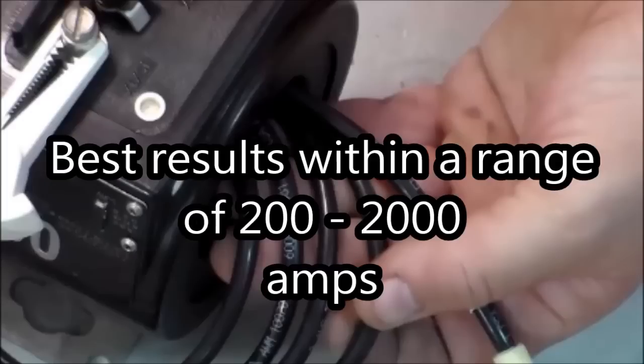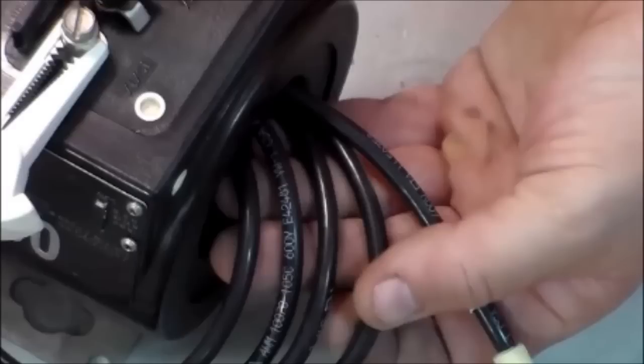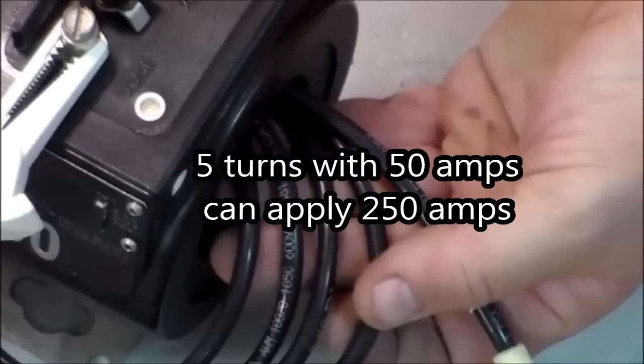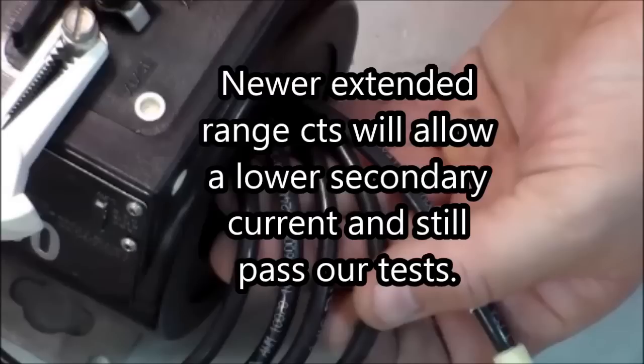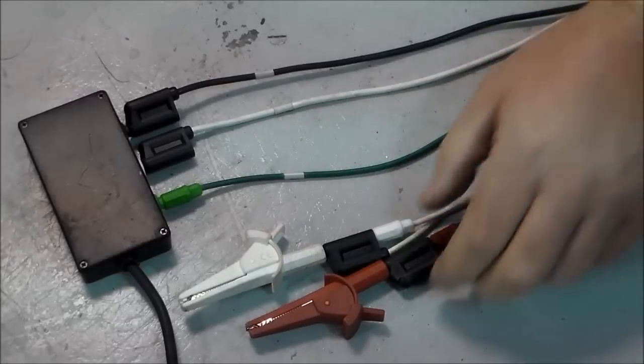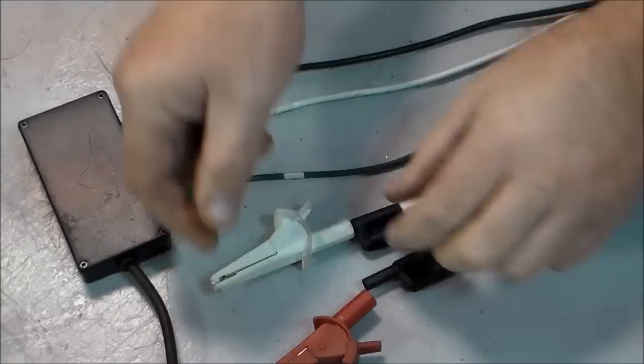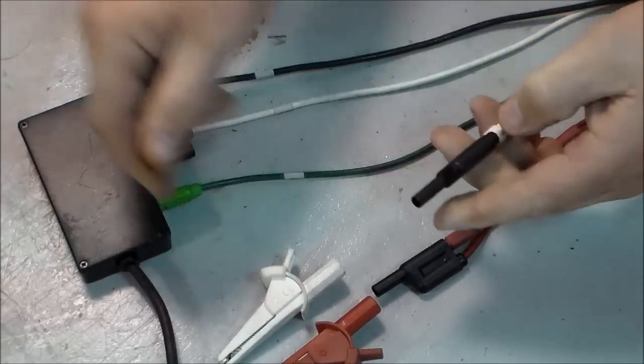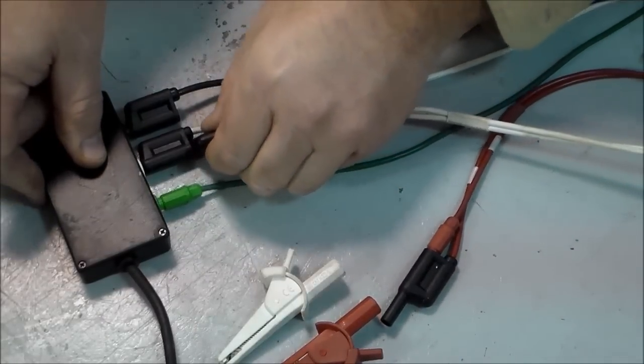As we move into the really large CTs, say a 2000 to 5 for example, we're approaching an upper limit of our test set. Again, we're going to see the best results in that window of accuracy, but in this case, we're not going to be able to get to the 2000 amps. About the max you can get is 250 amps, but that should still be able to test 99% of our CTs. Keep in mind the new extended range CTs have a wider window, so the lower end is even better. And lastly, we'll hook up our voltage cables. We'll just piggyback them onto our AC adapter box.